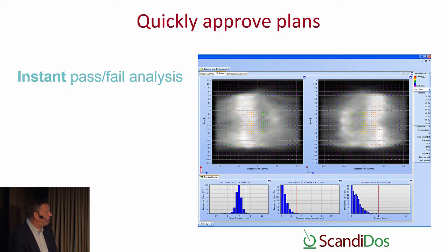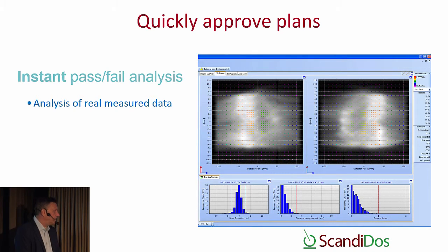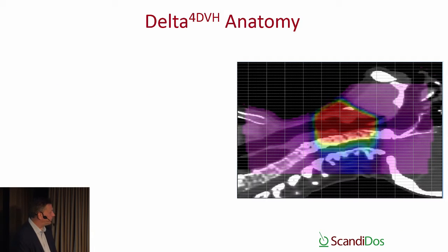The Delta4 system brings you many good things in the software, and it's known to have very strong software. One thing that you get is the instant pass and fail analysis. Immediately, instantly after you perform your measurement, you get the knowledge of whether it's a pass or fail on that specific patient plan. You do get analysis of real measured data, no additional processing, and then you get your green light.